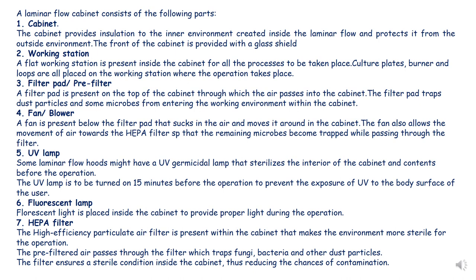Next is the UV lamp — in some laminar flow cabinets a UV lamp is provided, in others it is not — which kills microbes present inside the cabinet. There is also a fluorescent lamp which provides proper light during operation. The most important part is the HEPA filter — High Efficiency Particulate Air filter — present inside the cabinet, which makes the environment more sterile. Pre-filtered air passes through the HEPA filter, which traps fungi, bacteria, and other dust particles, ensuring sterile conditions and reducing the chances of contamination.